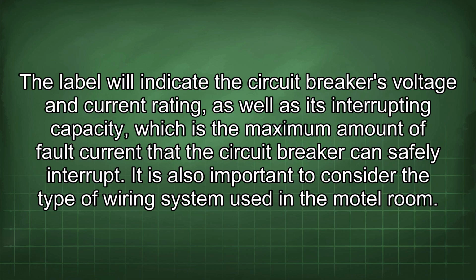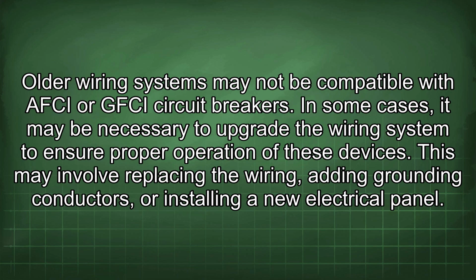It is also important to consider the type of wiring system used in the motel room. Older wiring systems may not be compatible with AFCI or GFCI circuit breakers. In some cases, it may be necessary to upgrade the wiring system to ensure proper operation of these devices. This may involve replacing the wiring, adding grounding conductors, or installing a new electrical panel.